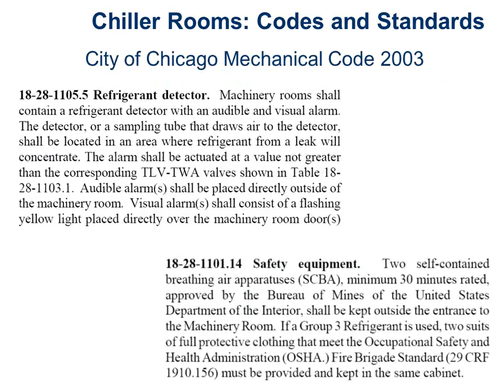This is what a particular mechanical room might look like. Let me see if I can get my little pen going here. Right, so over here I have an R22 chiller on the bottom right, so here's a sensor for him. I have several 123 chillers, so there's a sensor there, a sensor there, a sensor there. Pretty much one for every one. It's possible, depending on the distance between these 2 chillers right here, I might have been able to put 1 sensor in and cover both of these guys. But just from a general practice standpoint, it's easier just to put 1 in for every chiller and be done with it. Plus, that way, when they change 1 chiller out and it's a different refrigerant type, it's not some weird thing. It's like, oh, I just need to change the sensor out. I don't have to rewire stuff and run more conduit and try to figure out what the rules are. It's just done. One sensor per chiller is the way to go.